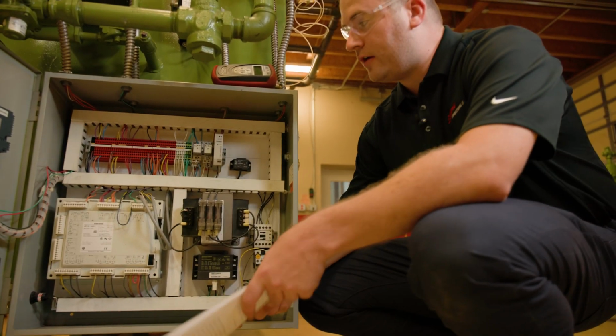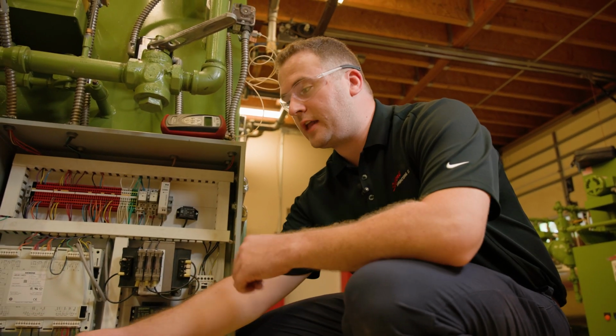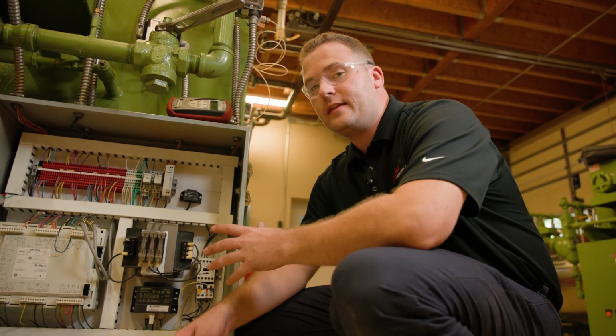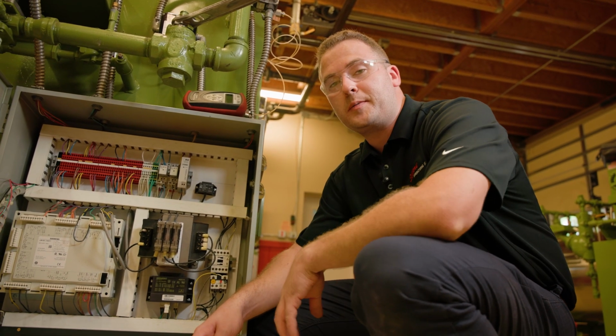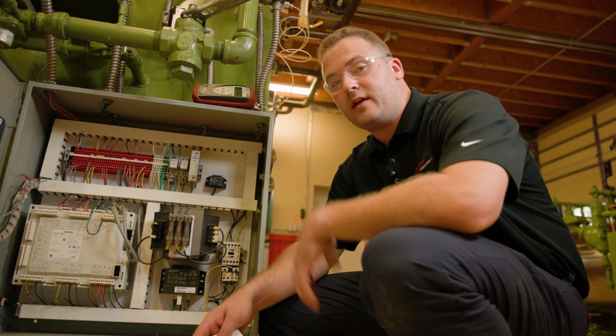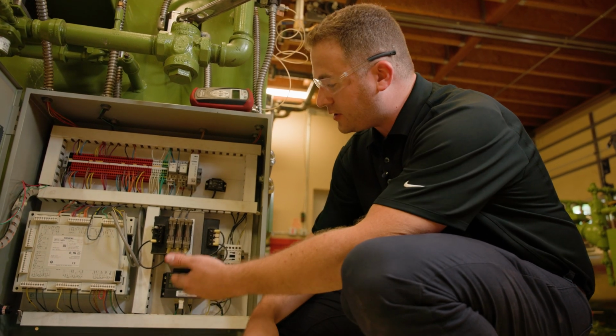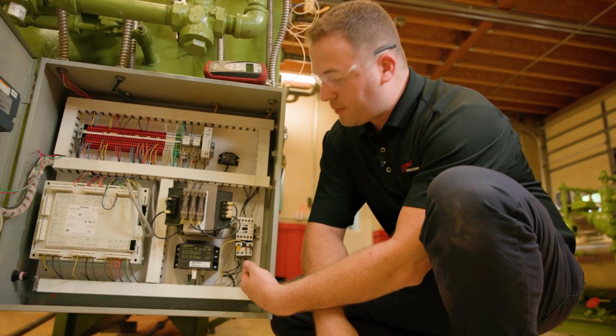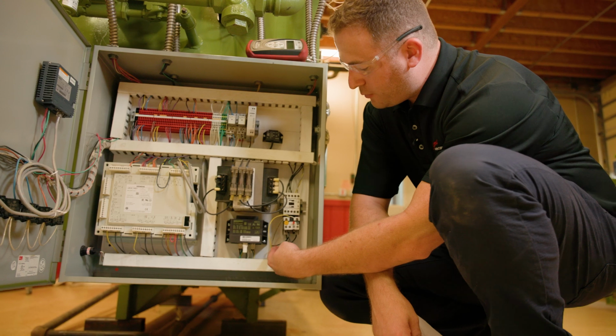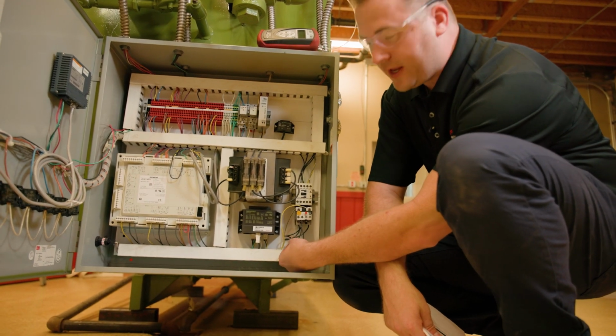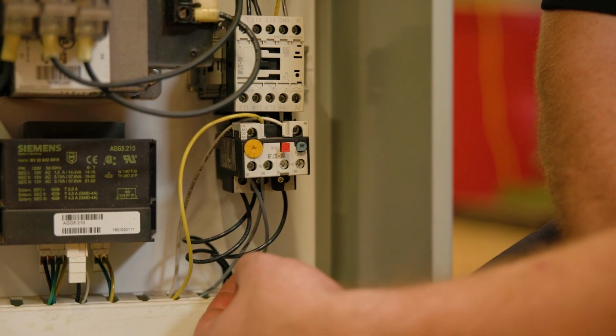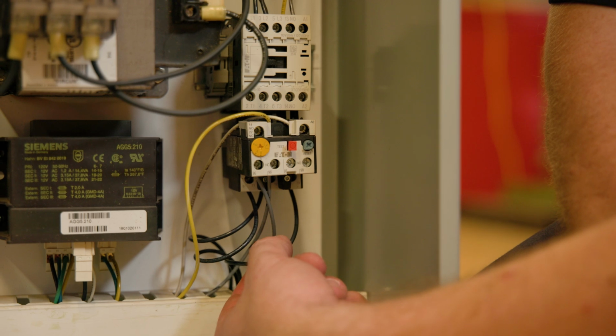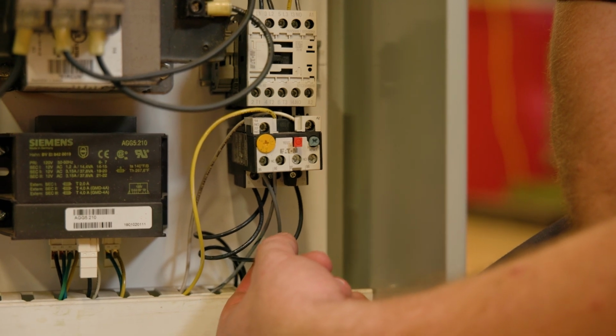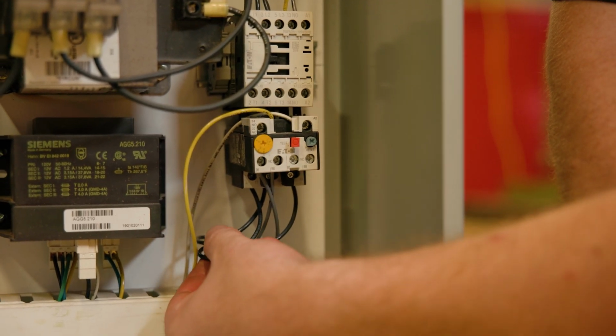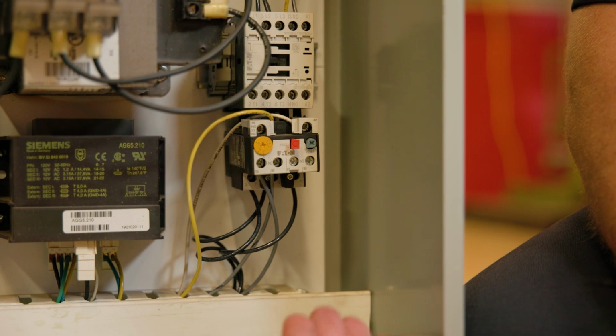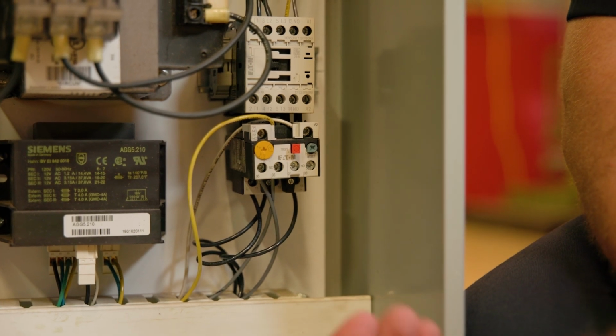Here in the electrical panel, you always want to be mindful of electricity, and if it's on, it's going to be on, so always wear the proper PPE. Right now we have the panel de-energized, but you're going to measure your blower amps. We have our motor starter on the side here, and we have L1, L2, and L3. You're going to take your amp clamp and only connect it on one wire. So you're going to take L3, L2, L1, and the amperage should be about the same across all three legs.